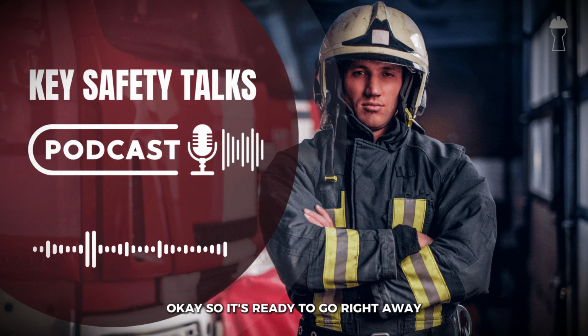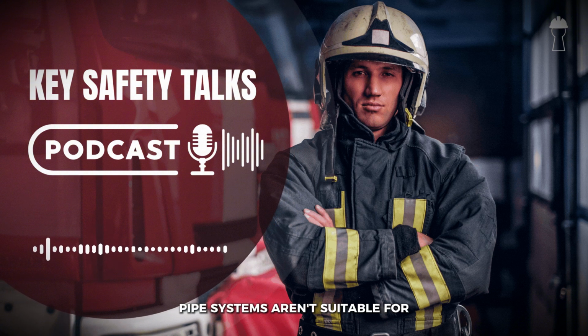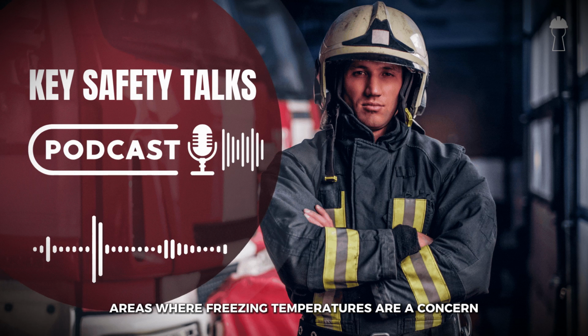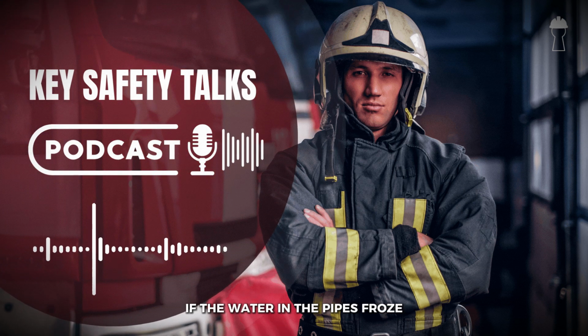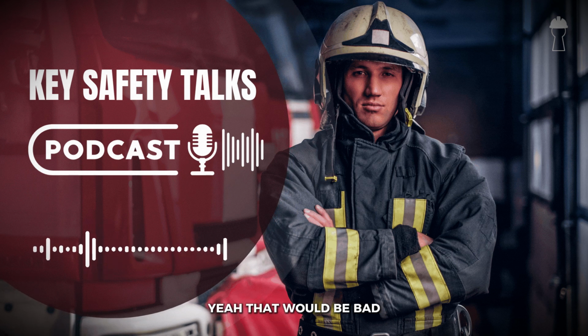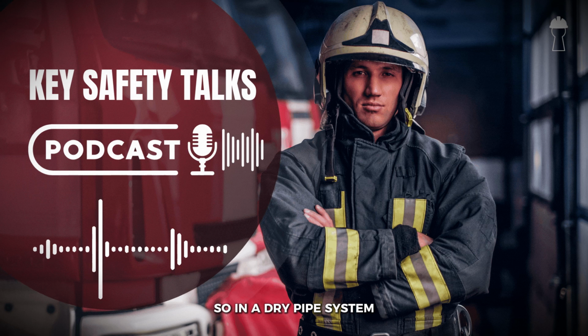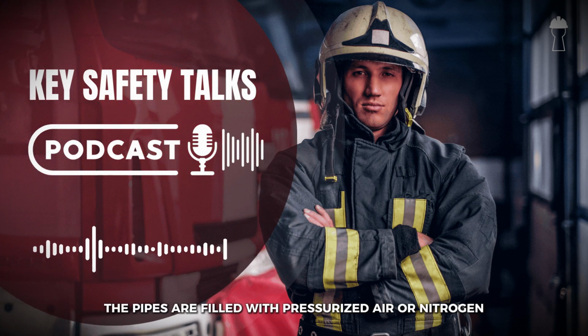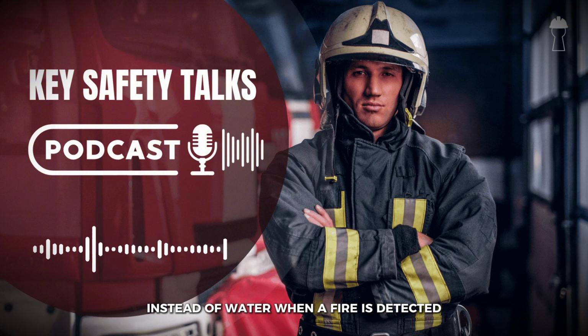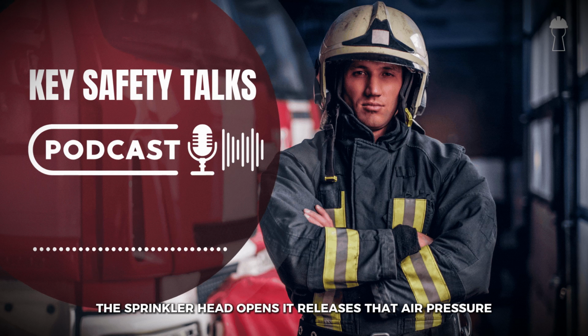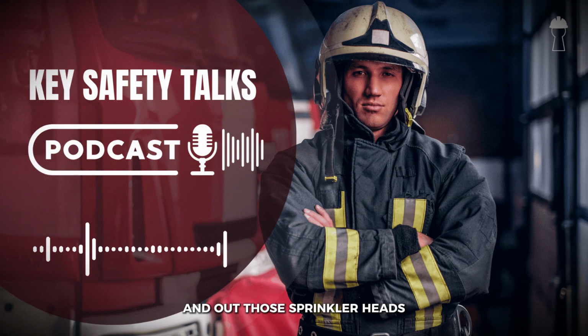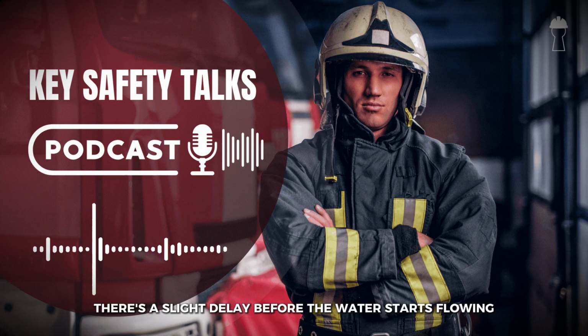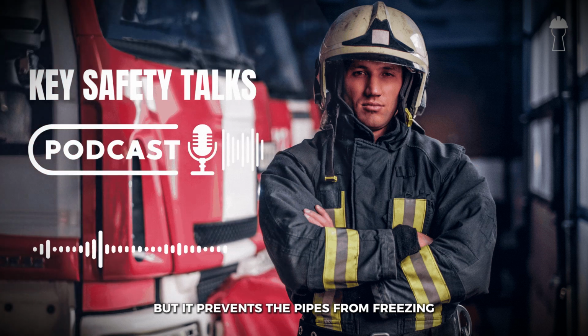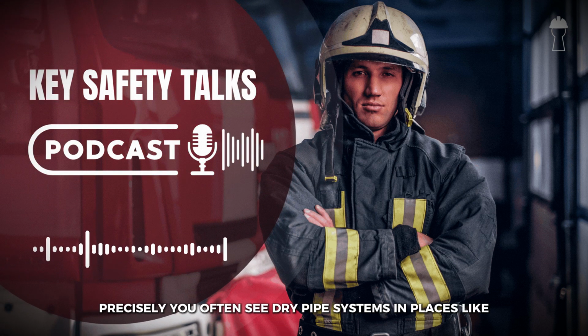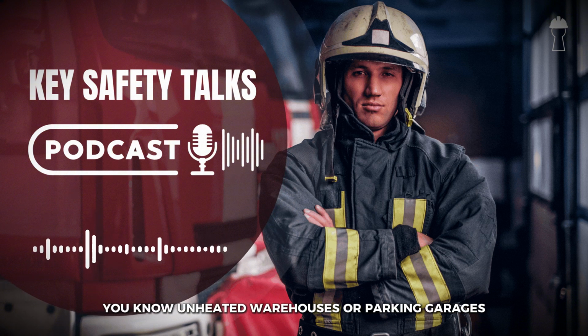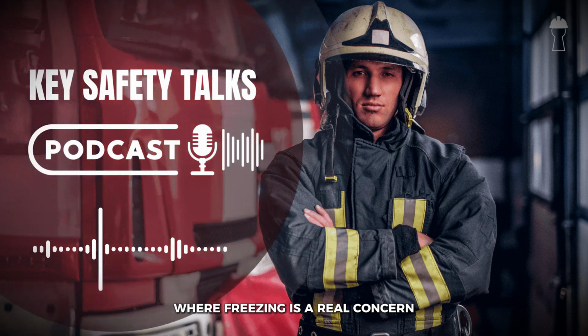Okay, so it's ready to go right away. It is, but there's a catch. Wet pipe systems aren't suitable for areas where freezing temperatures are a concern. I mean, can you imagine the damage if the water in the pipes froze, expanded, and burst those pipes? Yeah, that would be bad. So that's where dry pipe systems come in, right? Exactly. In a dry pipe system, the pipes are filled with pressurized air or nitrogen instead of water. When a fire is detected, the sprinkler head opens, it releases that air pressure, and that allows water to flow into the pipes and out those sprinkler heads. Okay, so there's a slight delay before the water starts flowing, but it prevents the pipes from freezing in colder environments. Precisely. You often see dry pipe systems in places like unheated warehouses or parking garages where freezing is a real concern. Okay, that makes sense.